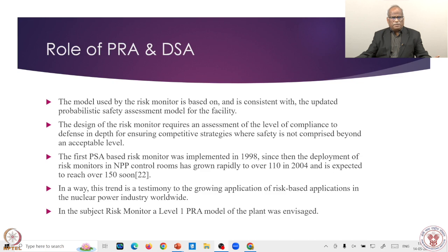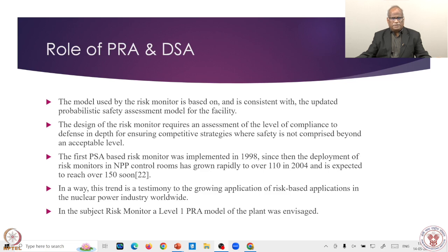PRA provides a complete integrated model of the plant and a quantified statement of risk: core damage frequency at Level 1. Level 2 is the risk of release out of the plant — the source term frequency. Level 3 is the risk to the member of public. This testifies to the growing application of the risk-based approach.